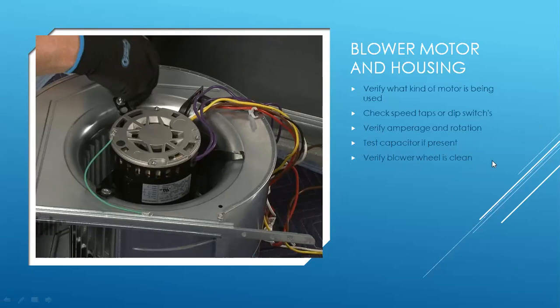And then verify your blower wheel is clean. That's how it should be. At least 8 out of 10 times when I did a blower motor, I always sold a blower wheel cleaning as well. Part of that is I would take the motor out, set that to the side, change it, but then completely clean this housing and the motor and the wheel. That way you're putting a brand new motor on a clean wheel as opposed to a brand new motor on a dirty, filthy wheel.